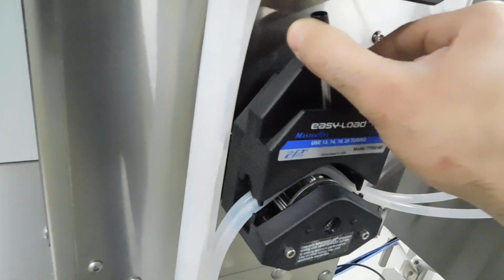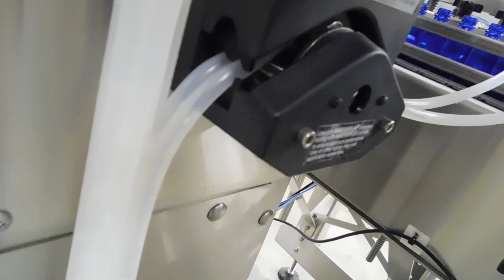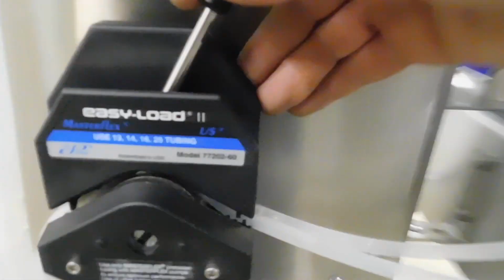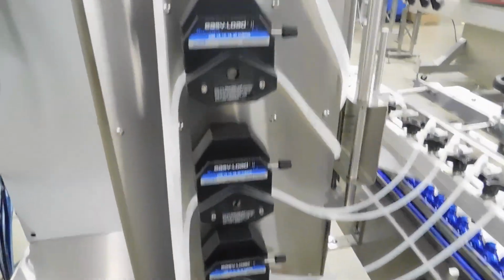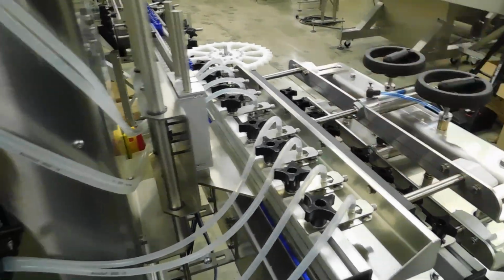Second one. And then you want to confirm that your tubing is passing into each channel and not crossing over at all. And here as well. We turn our handle to the right, watching to make sure the tubing is not getting pinched improperly. It should stay inside the V's, and push it all the way down until it clicks. Repeat this for all of your pumps. Each pump has 2 tubes, giving you your 8 filling heads.